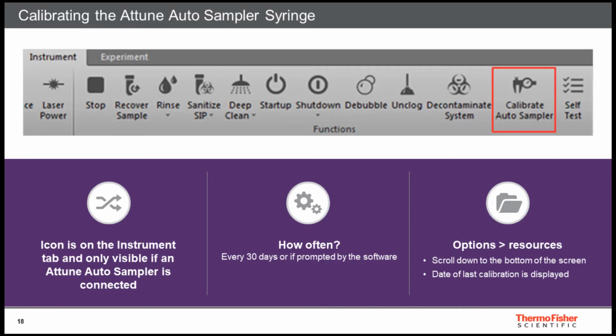Calibration of the Autosampler needs to be done every 30 days. The Autosampler will automatically go through a full calibration every 30 days. However, calibration can be run more frequently as needed.